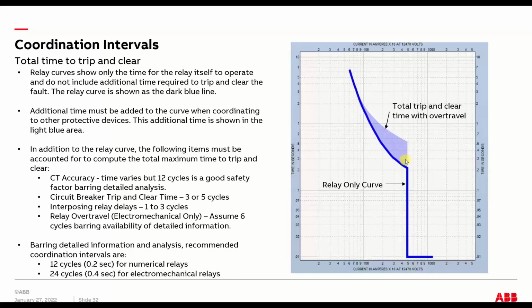So all those factors had to get added into the relay curve response so that you knew where you could set your next breaker. Your next breaker couldn't be anywhere except above here, or else you wouldn't be fully coordinated. In other words, you couldn't just draw the next breaker's curve right down this area, intersecting this hatch, because you would run the possibility of tripping both of them at the same time. They wouldn't be coordinated.